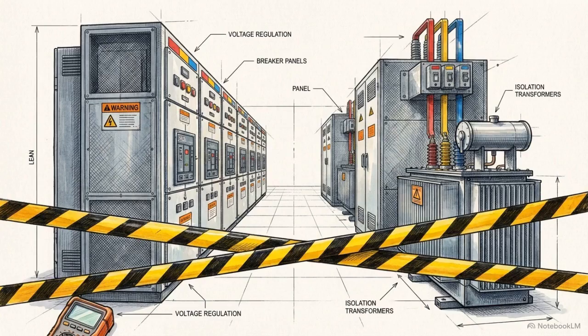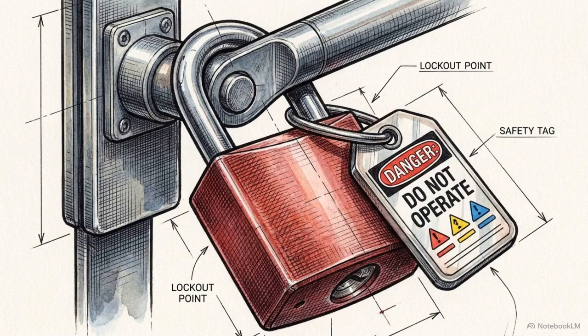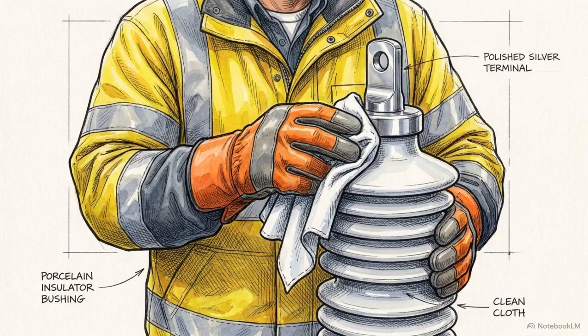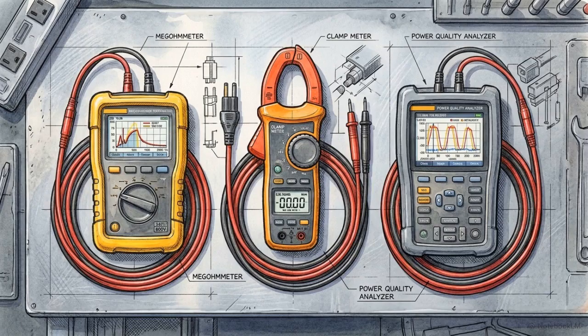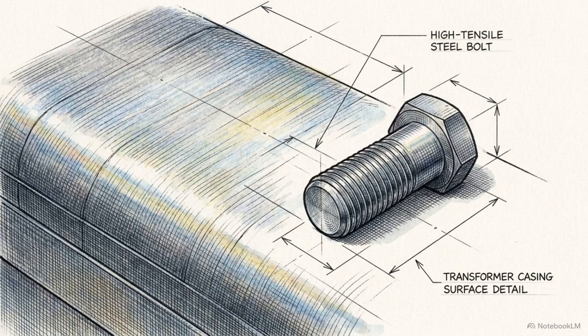Before a single meter is connected, the environment must be completely neutralized. This means verifying the lockout-tagout status, confirming temporary grounding sets, and meticulously scrubbing the terminal bushings to remove any conductive contamination or moisture. The validation matrix requires highly precise instruments. The testing sequence relies on 5 kV DC insulation testers, Doble power factor test sets, and calibrated microohm meters. Environmental contamination will structurally invalidate the entire dataset.